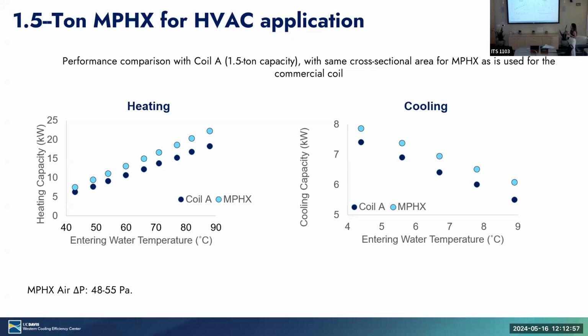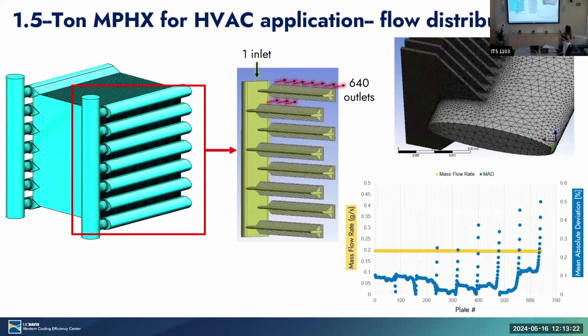So here I'm showing the heating and cooling graphs, which we're expecting for a wide range of temperatures to have a higher capacity in our heat exchanger than in the commercial coil. And as you see here, the pressure drop expected is around 50 pascals, which we could not achieve in a two-bank type of heat exchanger.